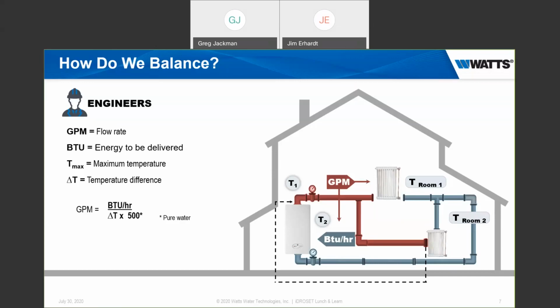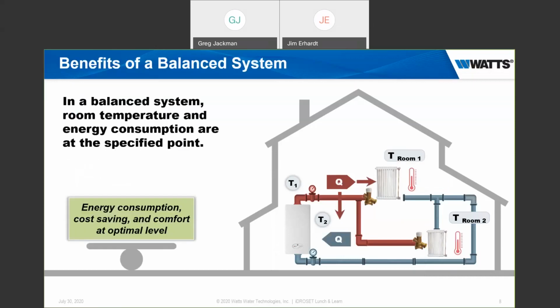And plus the pump itself will consume more electricity pumping a higher GPM than it will a lower GPM. So we really need to balance, but the primary reason we're going to balance, aside from all those other reasons, is to ensure maximum comfort to the occupants inside that building. In a balanced system, we're going to have all the benefits I just described. We're going to have flow that is appropriate to each of the heat emitters or cooling fan coils.